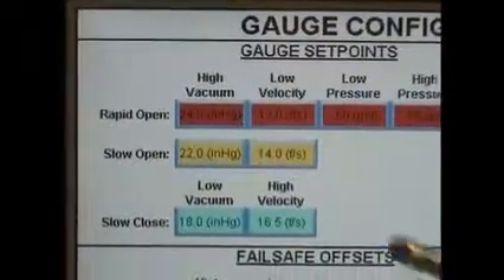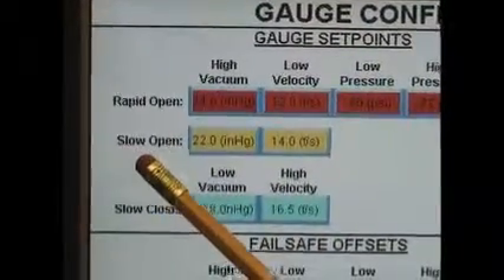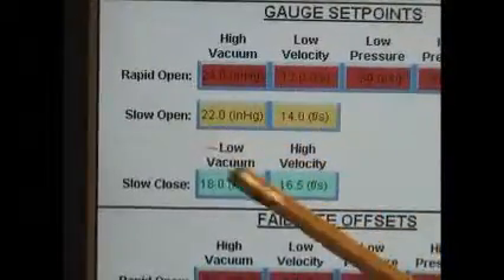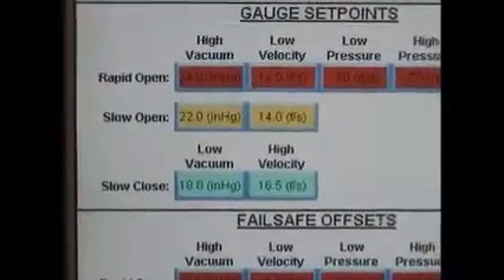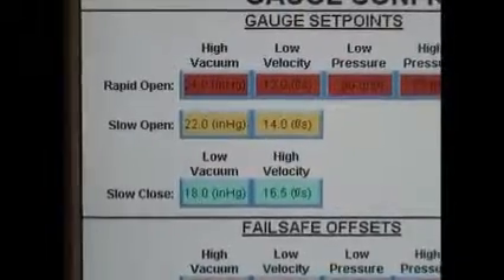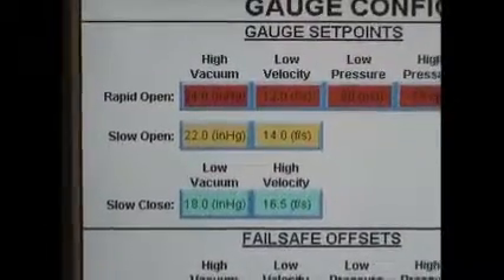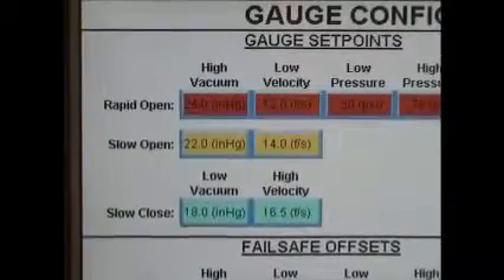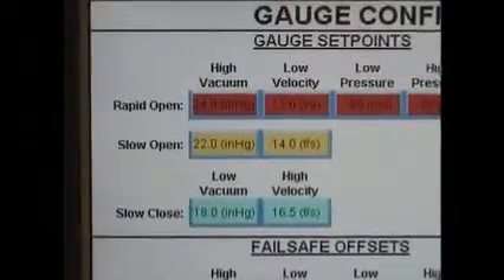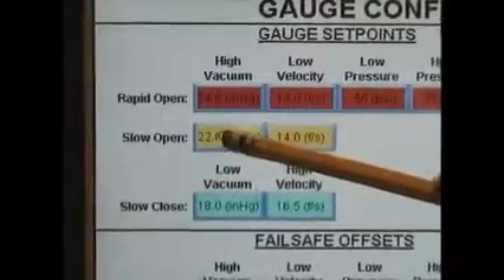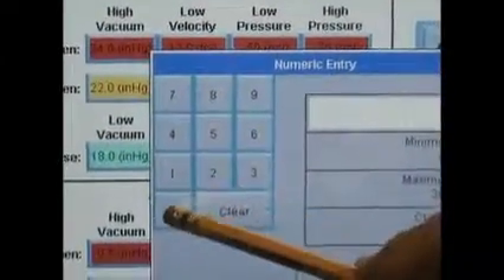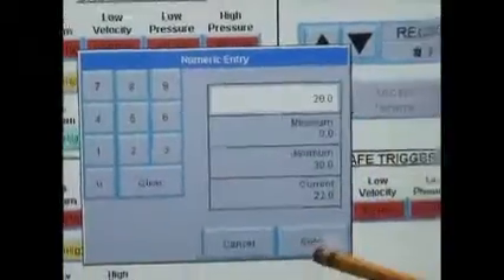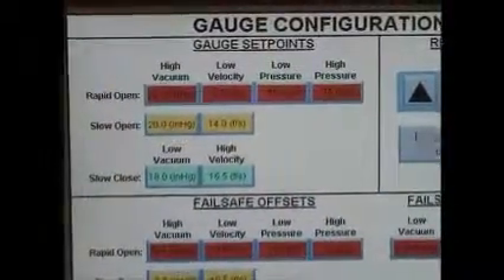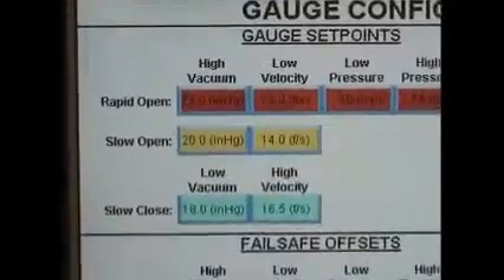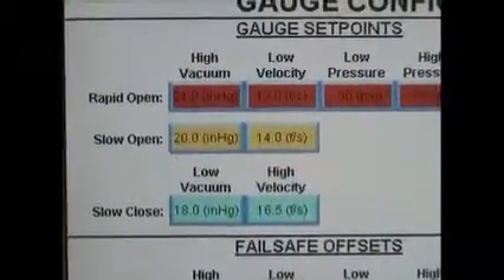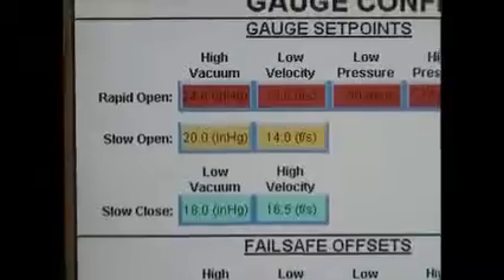or millimeters of mercury, either or. The next position is our yellow zone, where we want to start to step the valve open to introduce fresh water into the suction side of the inlet pipe, the vacuum pipe. Let's say we want that to start opening at 20. So we're going to enter 20 here and hit enter.